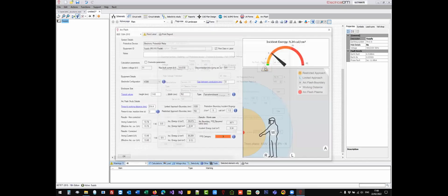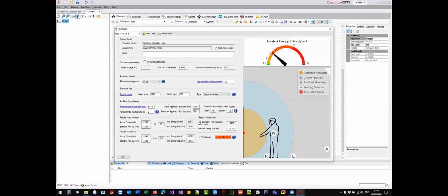So by clicking here, we see that we are accessing the arc flash calculator for this specific location. So we are at the medium voltage panel. From here, we can see that we're using the IEEE standard to perform the calculations. We support the 2018 standard and also the older 2002 standard, but we recommend using the latest one. Now, in terms of the interface here, you can see that we have included all the necessary information for you to review and adjust to perform a comprehensive arc flash study calculation and inspect all the relevant parameters.